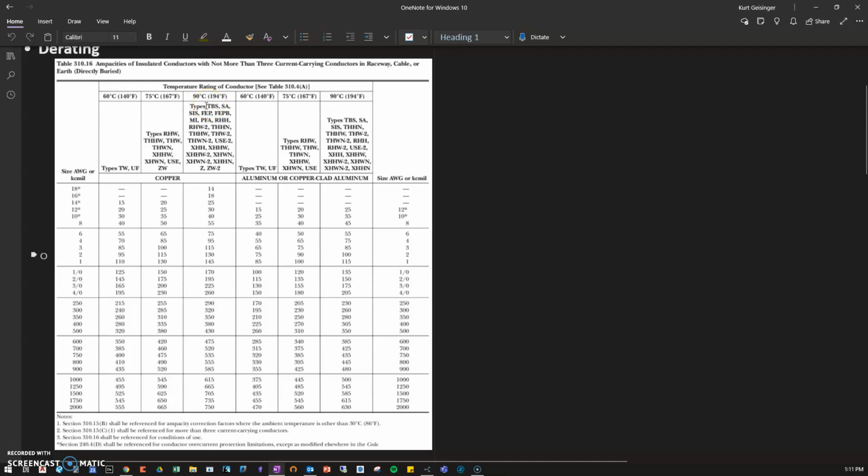What that means is when I do my derating calculations, I'm going to say, what type of insulation do I have? I'm going to find it in whichever column. That's the column I'm going to use to start my derating calculation. I point that out because, right at the beginning of this test, and I've said it before myself, if you're not told otherwise in this class, and we're just trying to say, what size wire do we need for this many amps?